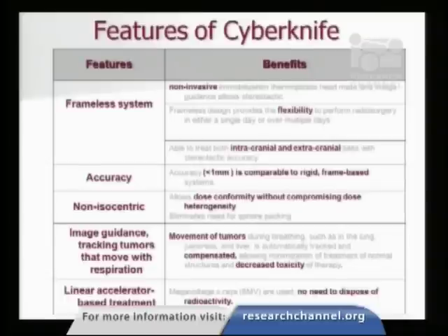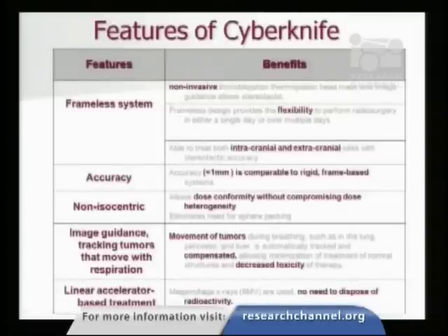The main features of the CyberKnife are that it's non-invasive. It allows more flexibility — with a frame device one would have to deliver all treatment in a single session, but without the rigid device, treatment can be delivered over multiple days. This opens up the platform to treat not only things in the head region but also outside of the brain. The accuracy is comparable to frame devices, as confirmed in many studies here at Stanford. The non-isocentric delivery keeps the dose conformal, and we can treat tumors that move with respiration with no need to dispose of radioactivity as with the Gamma Knife.